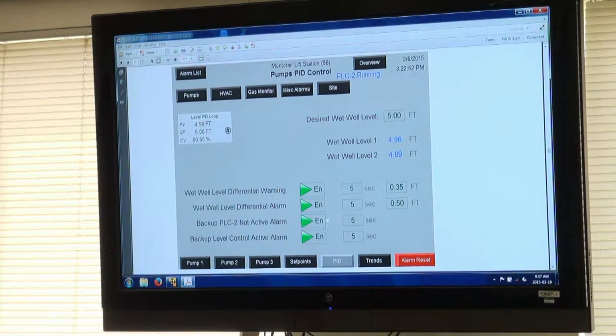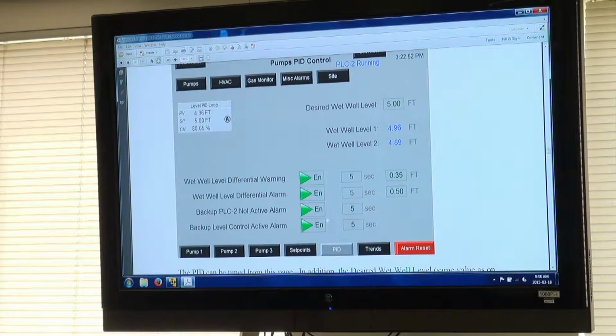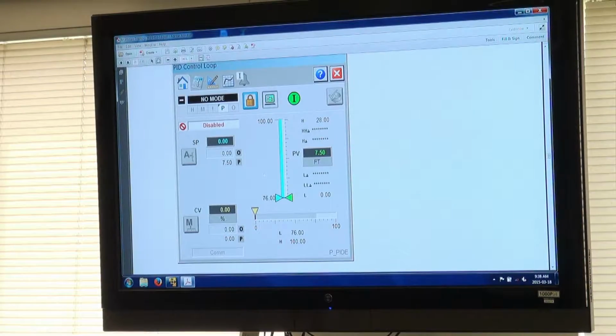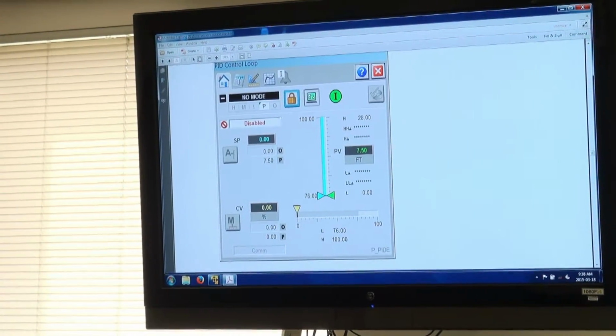Keep in mind with PLC 1 you actually have 2 processors there. So if one faulted, for whatever reason, the second would take over. You wouldn't notice. It would be seamless. You would get an alarm or a status back at SCADA, but you wouldn't actually stop running PLC 1. If you lost power in the whole cabinet, that's a different story. Now both processors are down, and that's why PLC 2 is there. Down here is our PID, the controls that we have.